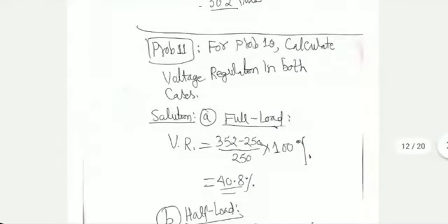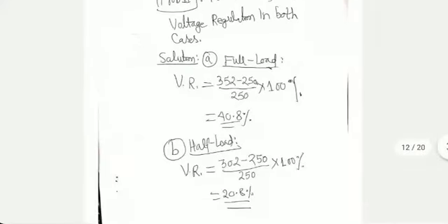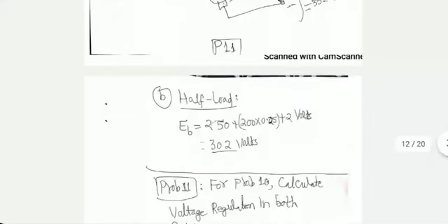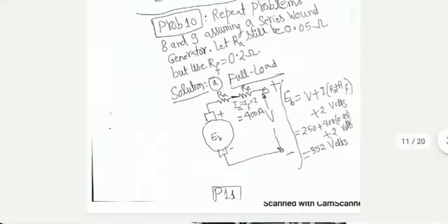Voltage regulation, you can calculate again using well-known equations. One thing very important that you see is the voltage regulation is quite bad in series wound DC generators. It is 40.8%, 20.8%. That is unacceptable practically. More than 10% is generally a no-no for all practical situations. The conclusion is that DC generators with series wound construction are simply not going to be used.